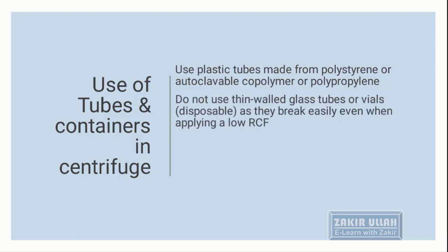Do not use thin-walled glass tubes or vials which are usually sold as disposable, because they are easily breakable even when we apply a low relative centrifugal force. This kind of cheap glass is very thin, and that's why we should not use such glass tubes in the centrifuge.